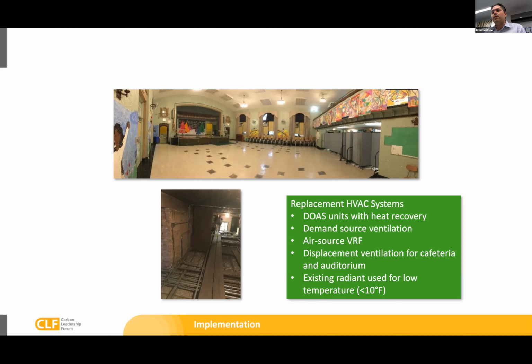If you see the picture on the top, that's their auditorium. Those little squares on the floor are actually the diffusers, so air's supplied low. We were able to upgrade those diffusers into a displacement style system to better provide air conditioning to that space and keep the supply low and limit the space conditioning to the lower level of that auditorium. Right now, that space has a couple of window units that really are insufficient.